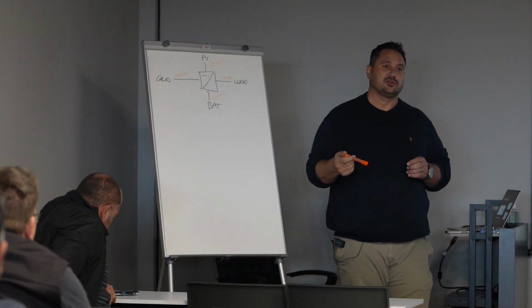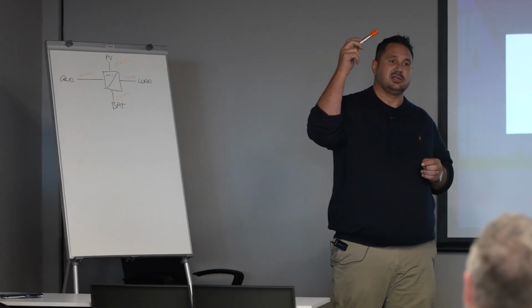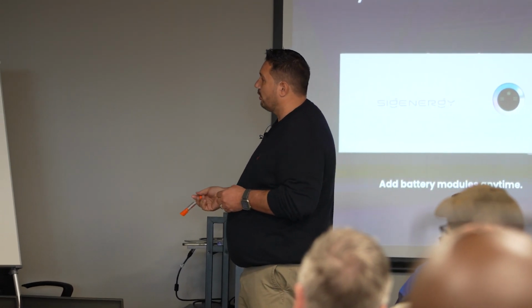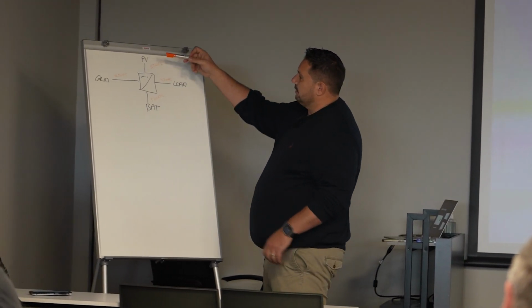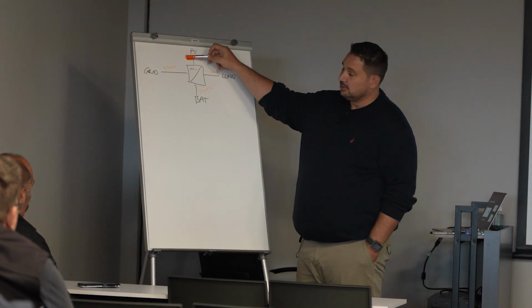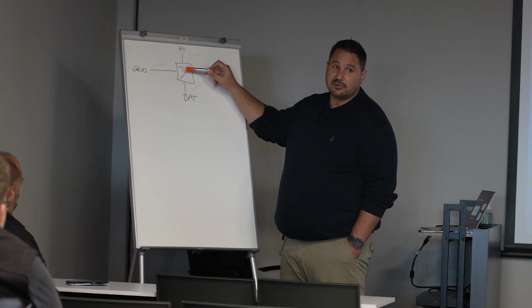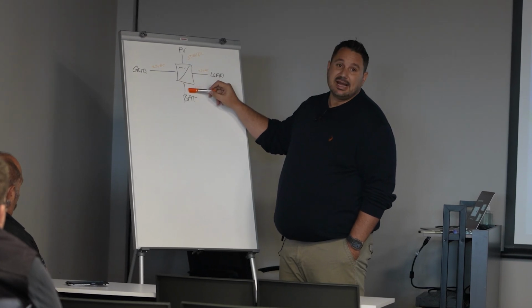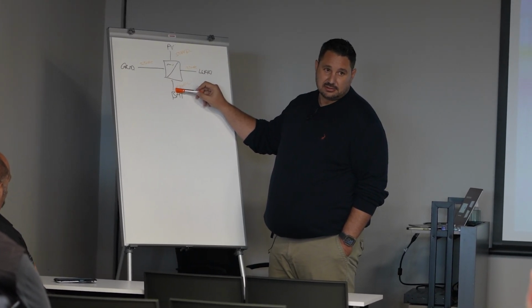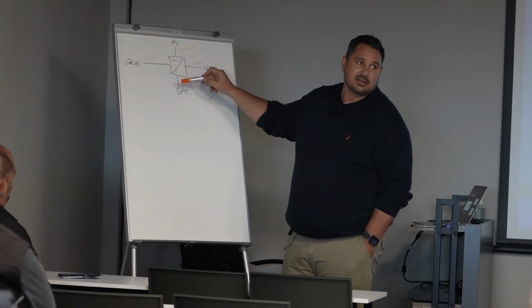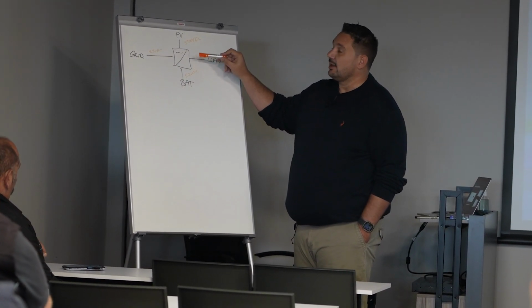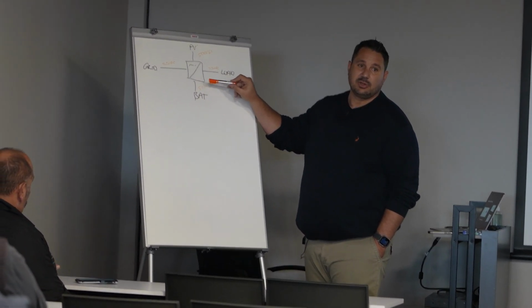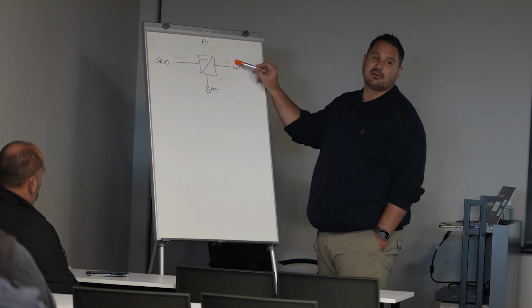Okay. So, if I want to use the PV generated tonight, we have to store it in a battery. So what are we doing? We're taking 500 volts DC, pushing it through a hybrid inverter, converting it down to 52 volts DC. How much losses do you think is actually happening inside there? Then we take 52 volts DC, we convert it back to AC, step it up to 230 volts, and then use it.